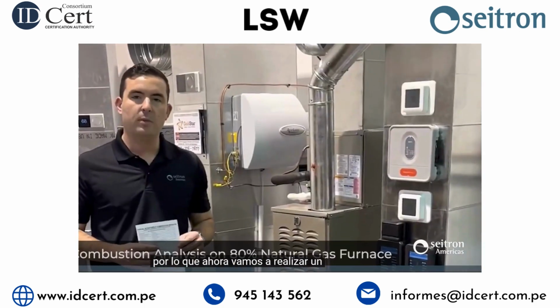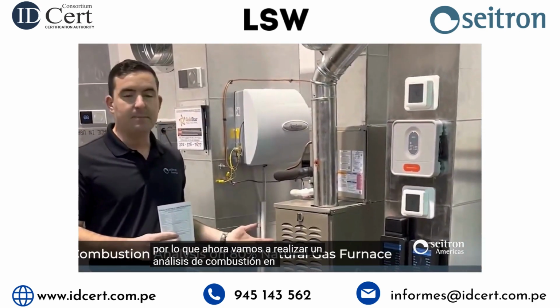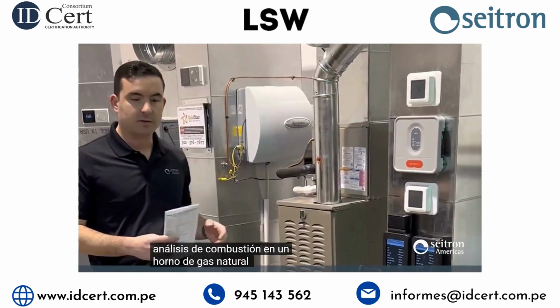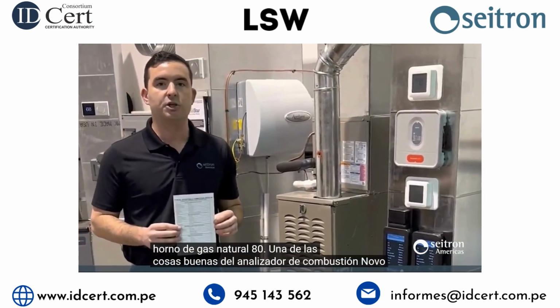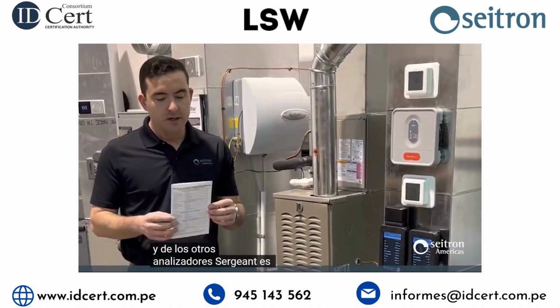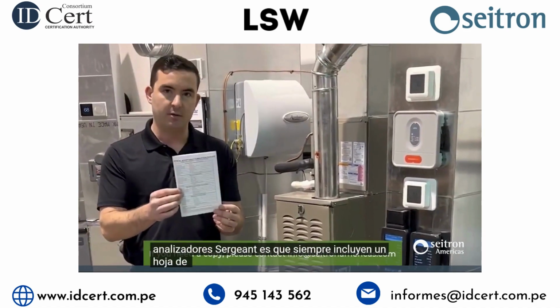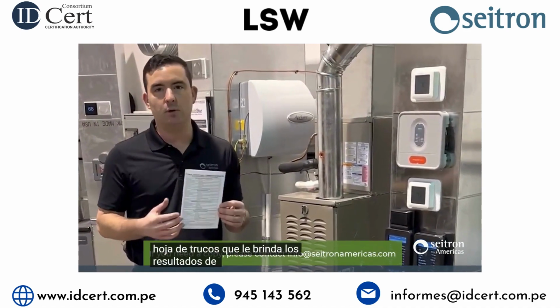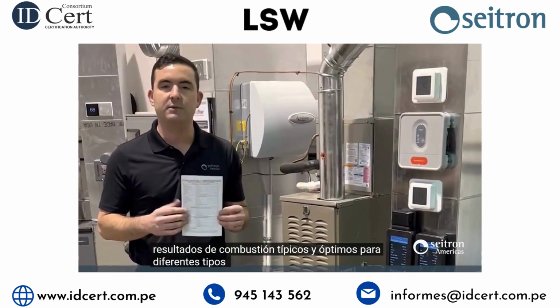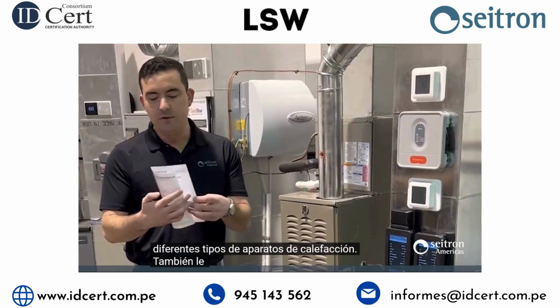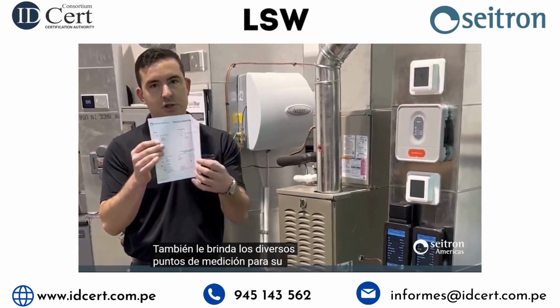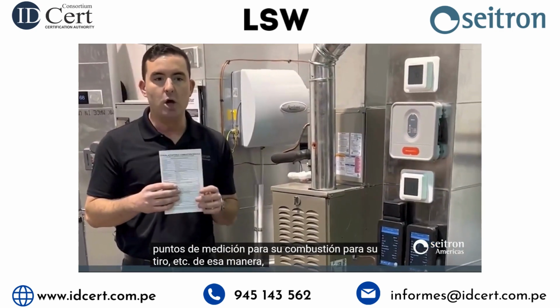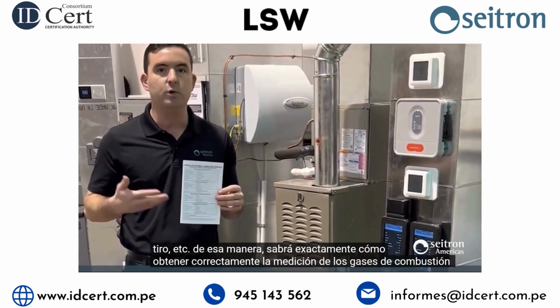So now we're going to perform a combustion analysis on an 80% natural gas fired furnace. One of the nice things about the Novo combustion analyzer and the other SEITRON analyzers is that they always include a cheat sheet, which gives you your typical and optimal combustion results for different types of heating appliances. It also gives you the various measuring points for your combustion, for your draft, etc. That way you know exactly how to get your undiluted flue gas measurement.